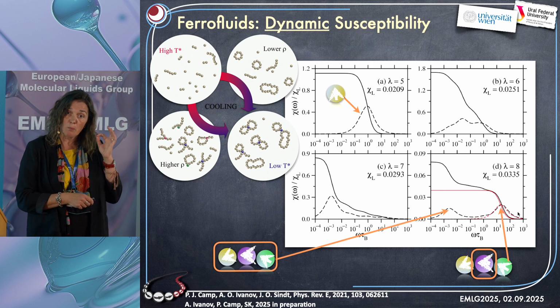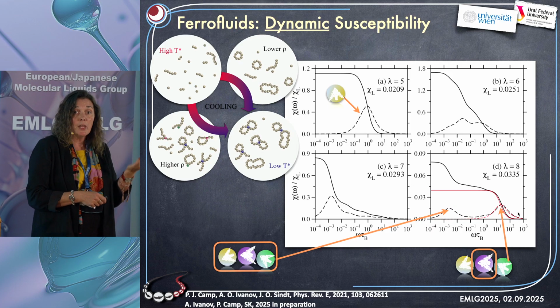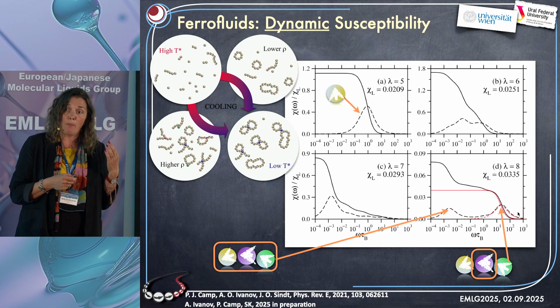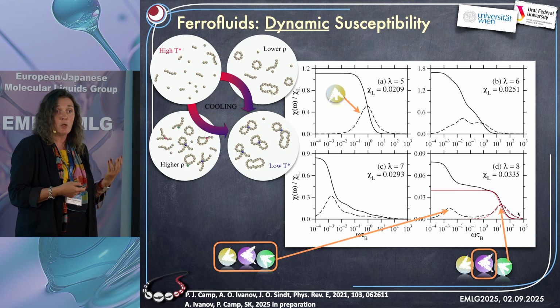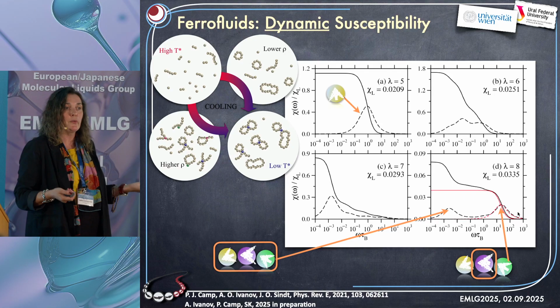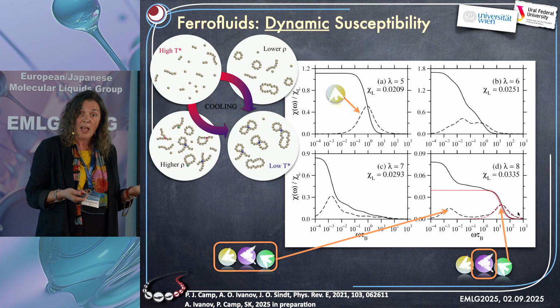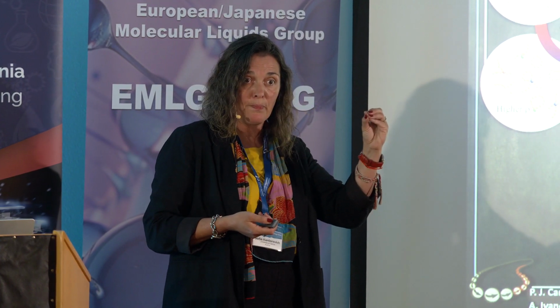Why is frequency important, and not only the amplitude of the field? There is a physiological limit to which frequency and which field strength you can apply to a patient. It's called the so-called Brezovich criteria. I mean, it is arguable, but it is one of the references currently on the market. And this is the product of frequency times amplitude.